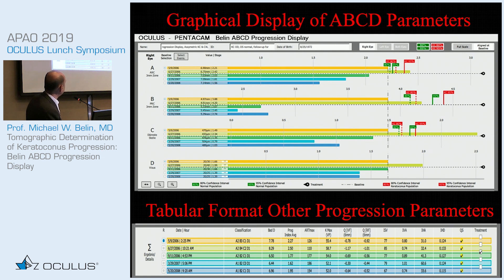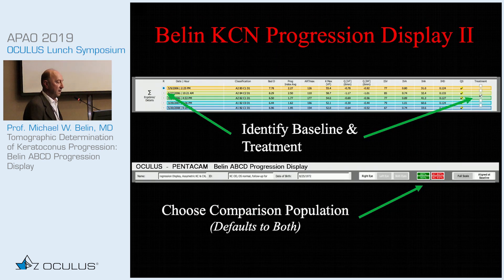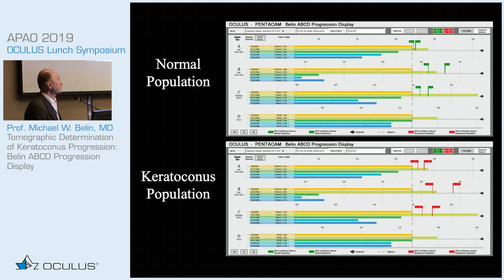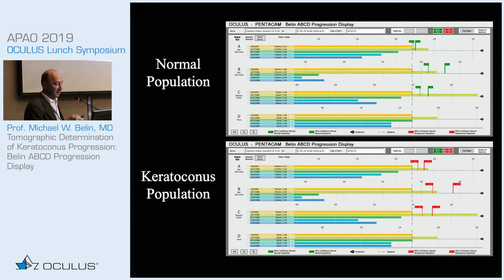The tabular section shows the classification, the progression index, ART max, and a number of anterior surface parameters historically used to determine progression. You can identify your baseline and mark when a treatment occurs. You can also choose your comparison population — either normal or keratoconic — with the default showing both. For very early or subclinical disease patients you should probably compare against the normal population, while more advanced disease should be compared to the keratoconic population.